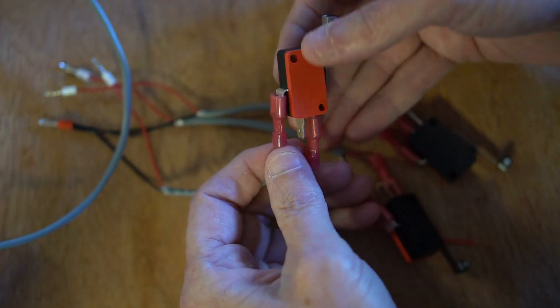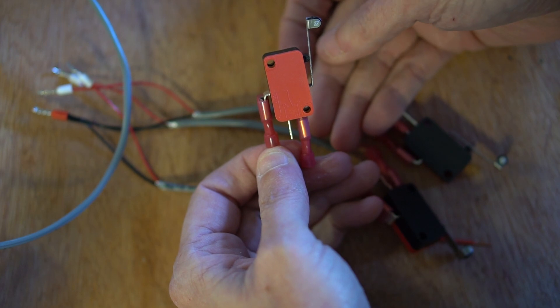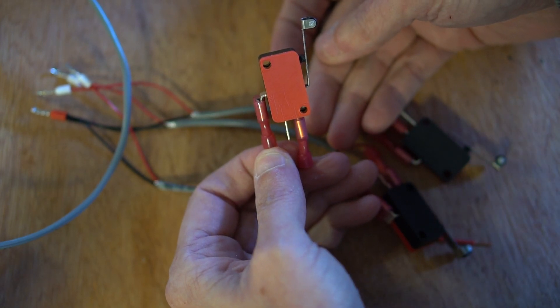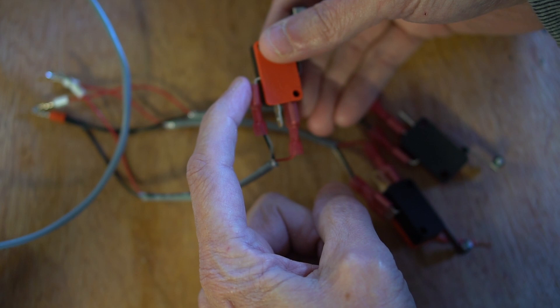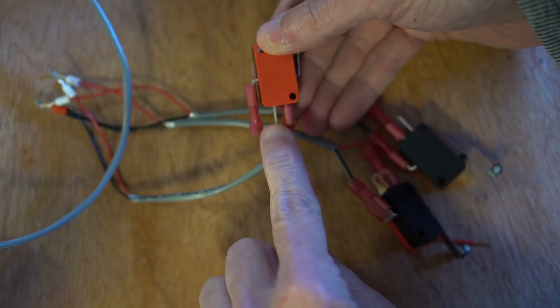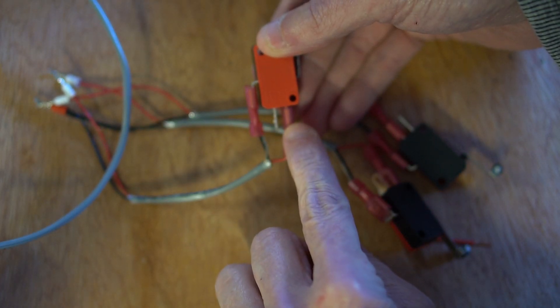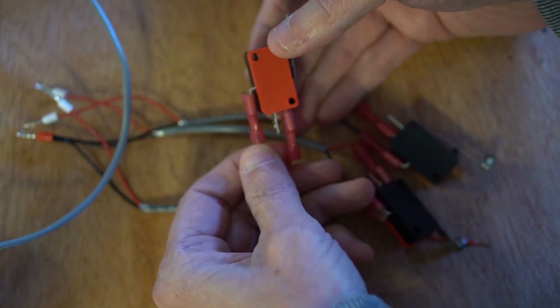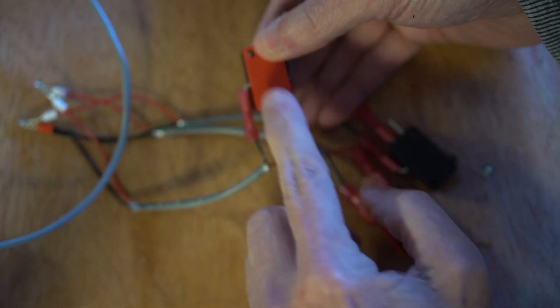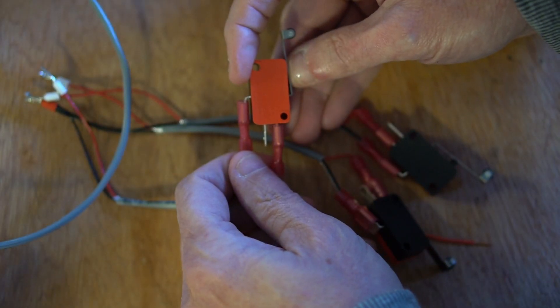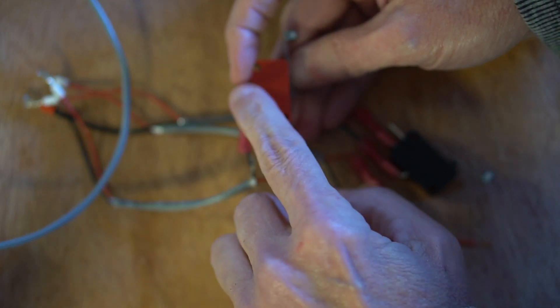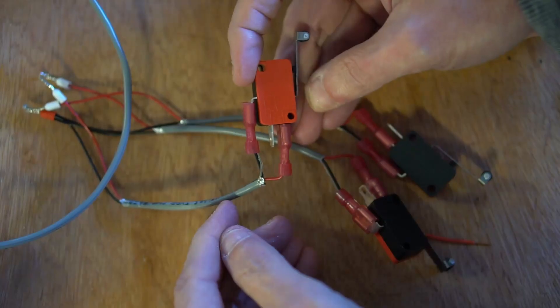You'll see on the switch itself that I'm wiring these switches in the normally closed configuration. This lead here is the common lead, where the ground wire is connected. This lead is the normally open lead, which is not connected. And this lead is the normally closed lead. When the limit switch is not engaged, these two wires are normally closed, or they are connected. When the switch is depressed or engaged, then that connection is cut, or it becomes open.